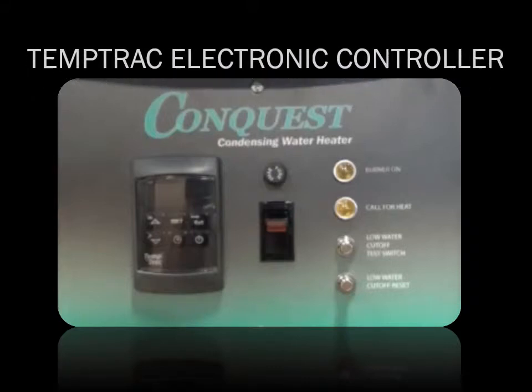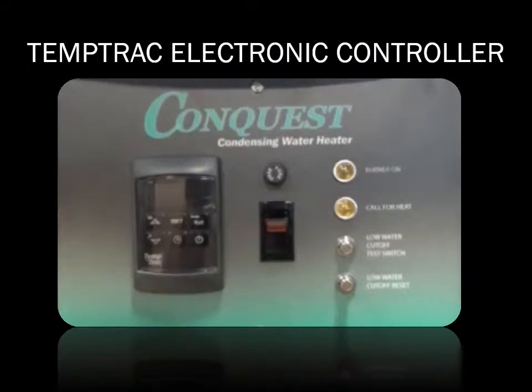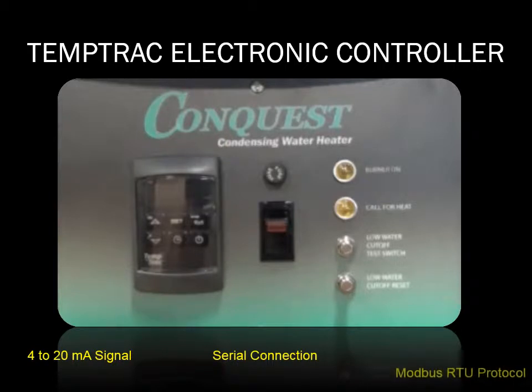This session reviews the features and operation of the Conquest Temptrac electronic controller. The Temptrac electronic controller provides accurate temperature control and outputs a variable 4 to 20 milliamp signal for modulating type products. It also provides a serial connection and Modbus RTU protocol for communication with building automation systems to provide notification of heater status, firing rate, and alarm conditions.